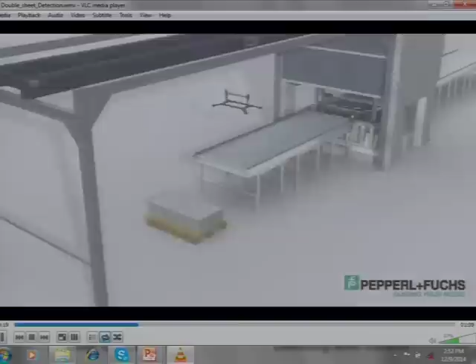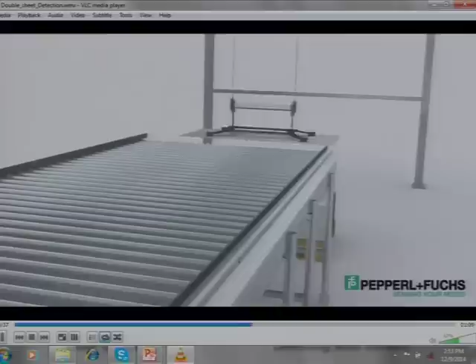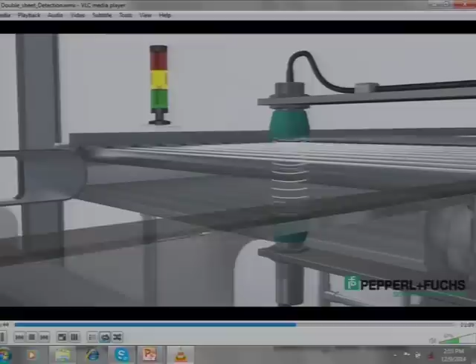Can there be any circumstance where there is a false alarm also? Any exceptional case, for example, where there are not actually two sheets? I have come across some applications where this had happened. It was because on all of the sheets they put a lamination, and the lamination was not uniform. There were certain air gaps inside it, and as a result of those air gaps, it was always detecting two sheets, even if there was a single sheet. So certain limitations are always there.